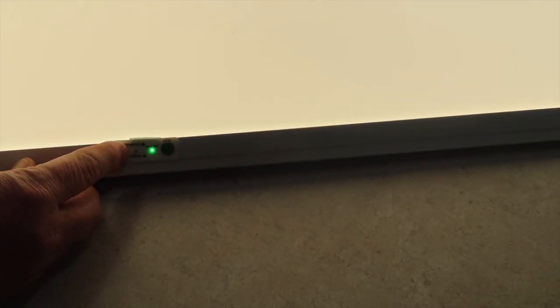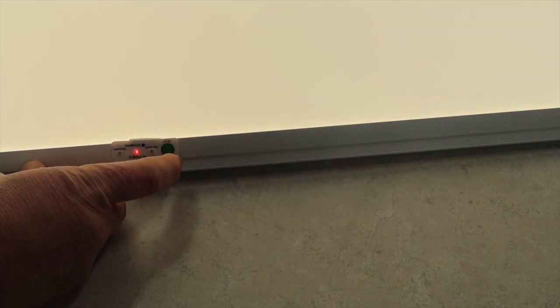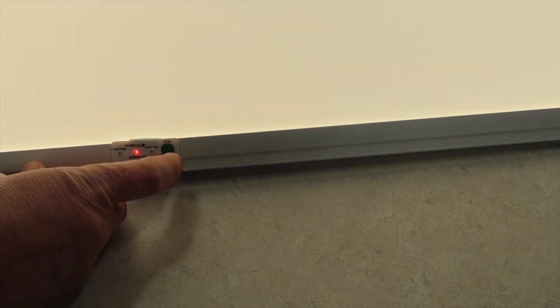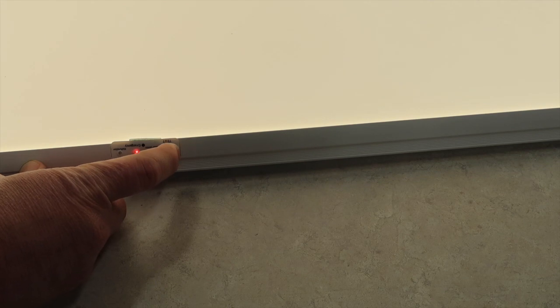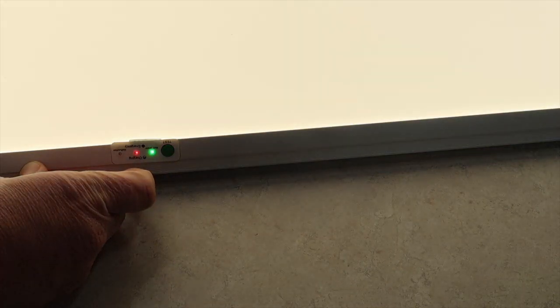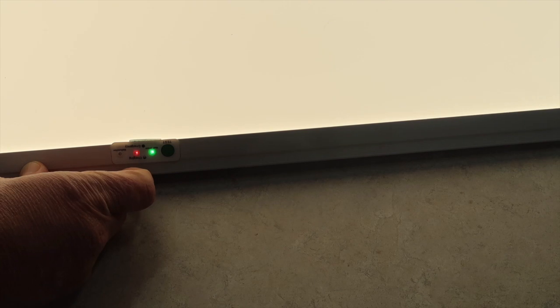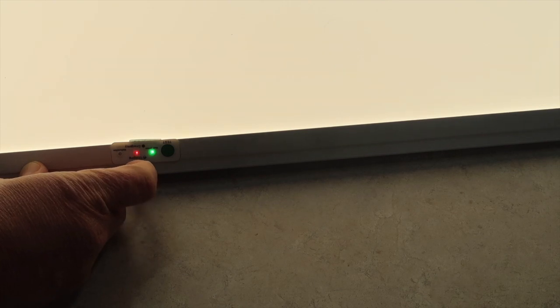And we're going to simulate a power failure. I'm going to give you the side and here's the test button for this. It says right now that that blinking light says it's charging. You now know this whole fixture is working. You see that blinking red light there. And I'm going to test it. Now you see it go through the test mode. Did you see it dim down? There it goes. Tested. Now we're going to simulate a power failure.